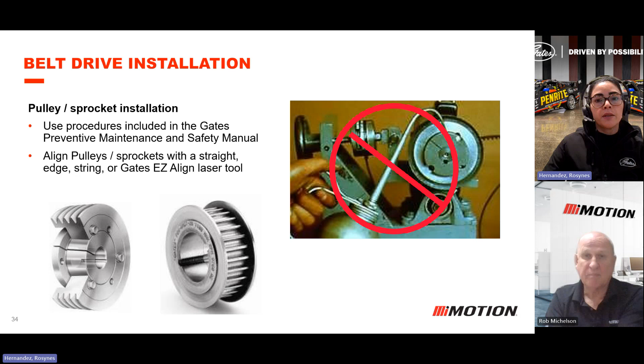Another important element is when the pulley isn't directly mounted on the shaft but uses a type of bush. You need proper installation of the bush—this depends on its size, and there are removal holes and installation holes. Sometimes these aren't clearly marked, so people confuse one for the other, which causes improper installation. Excessive torque on those holes can also damage the bush and the pulley.